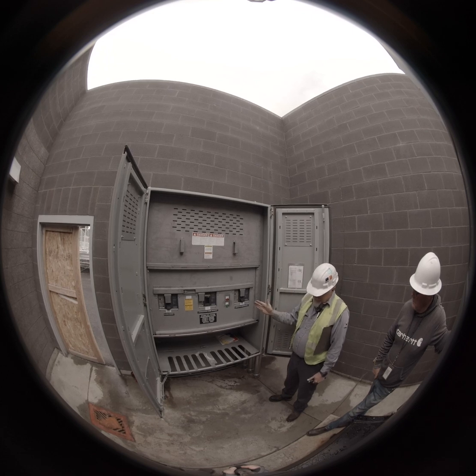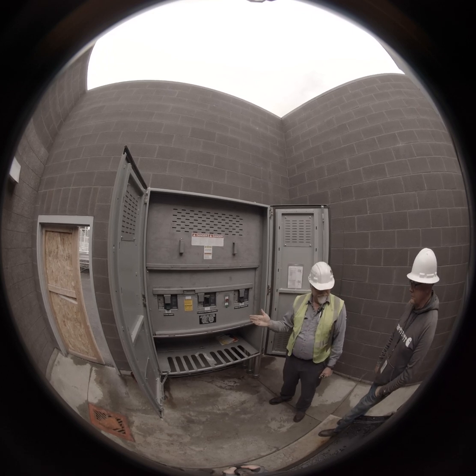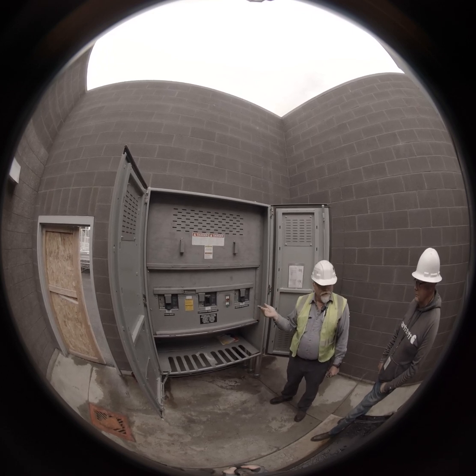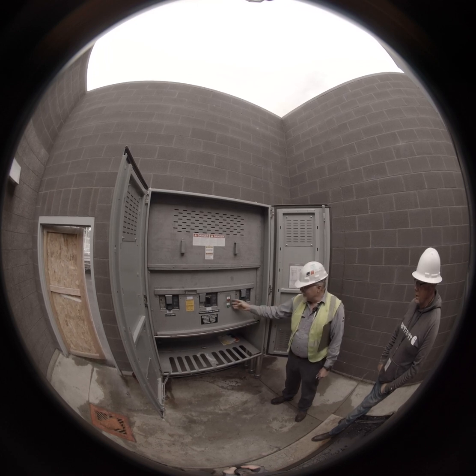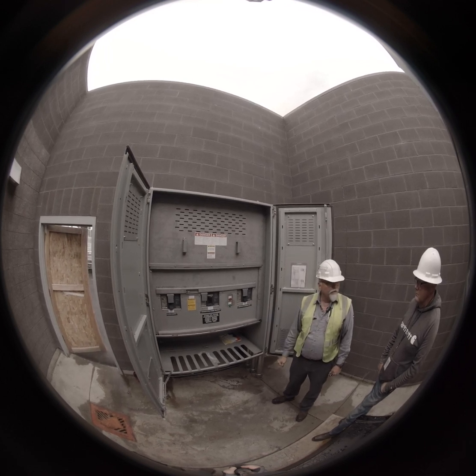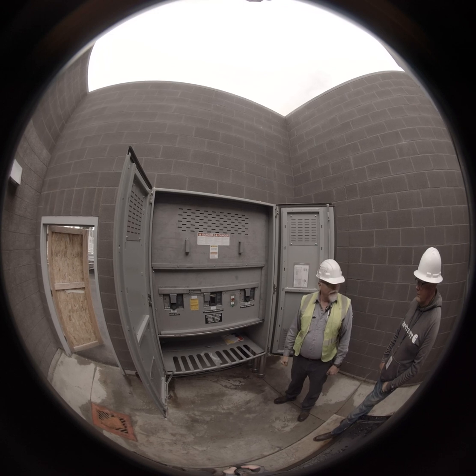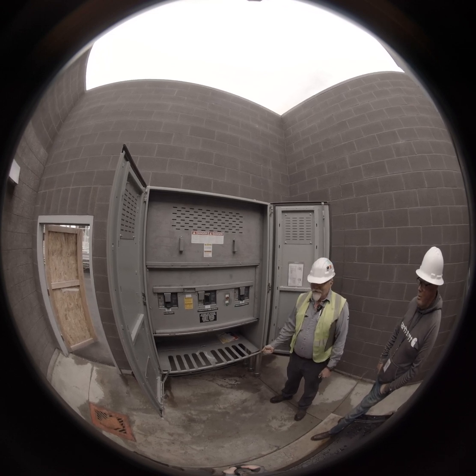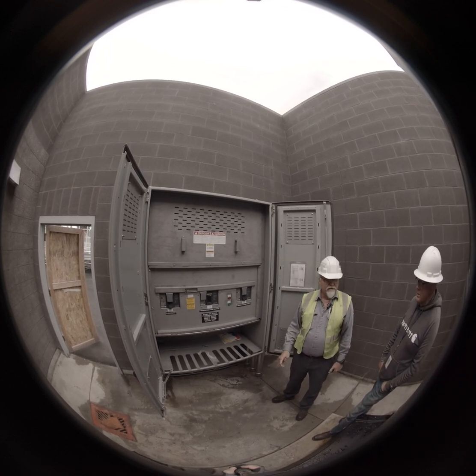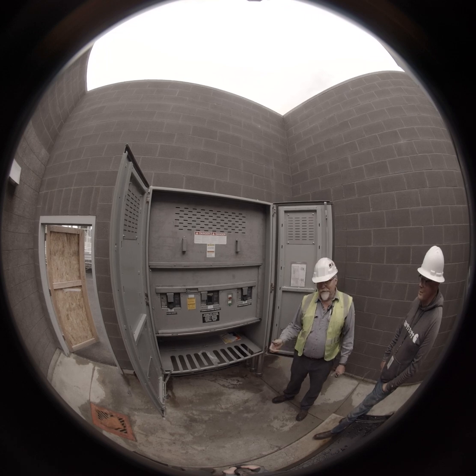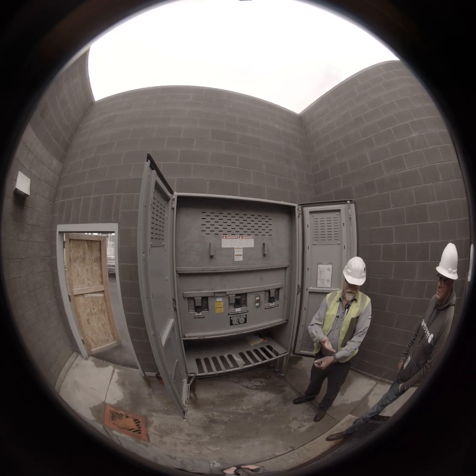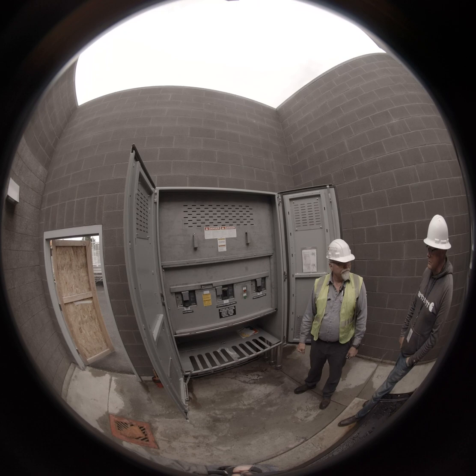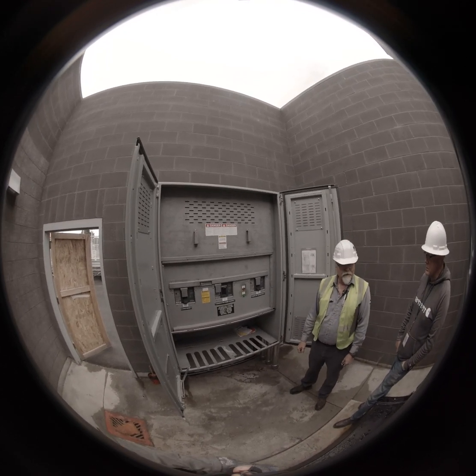When you fire up the temp gen, of course, you don't have utility anymore. So you need to know what your rotation is. This here has rotation lights on it, which will tell you whether you're forward rotation or not. Standard on most everything built nowadays is they are clockwise rotation. But if you're laying cable out, obviously you can spin them any way you wish, and it's easy enough to get them backwards.